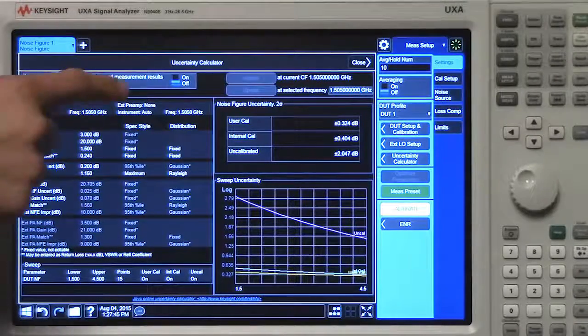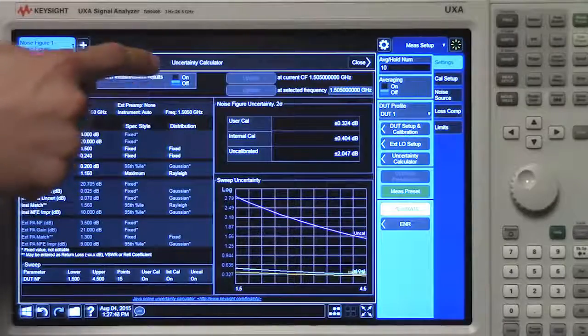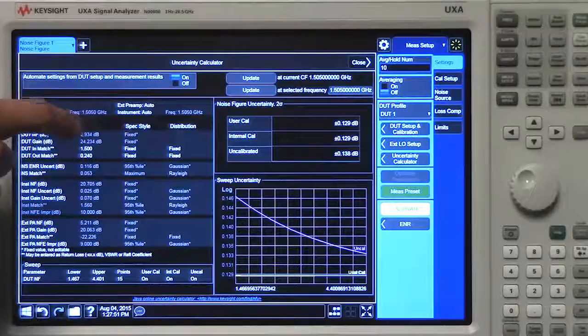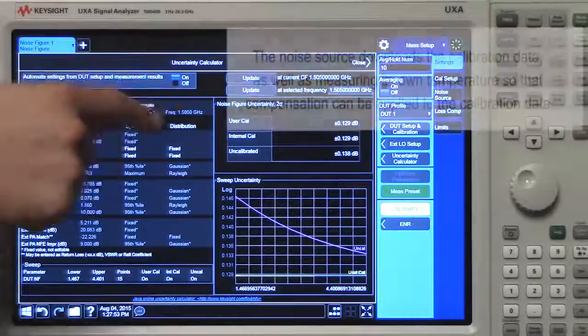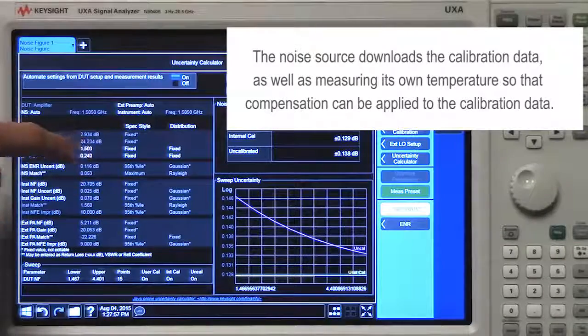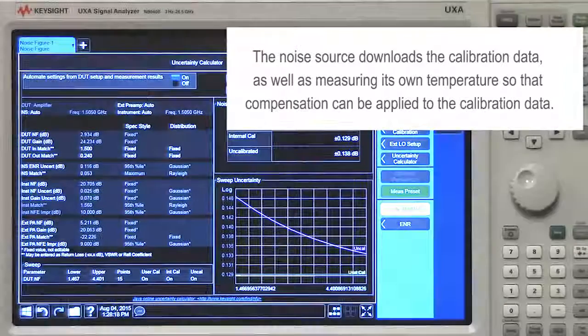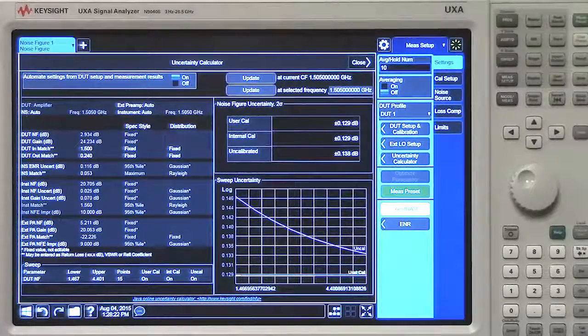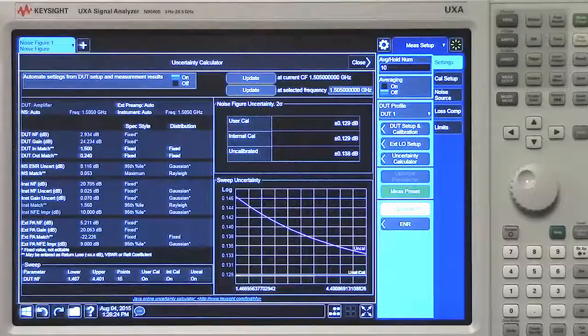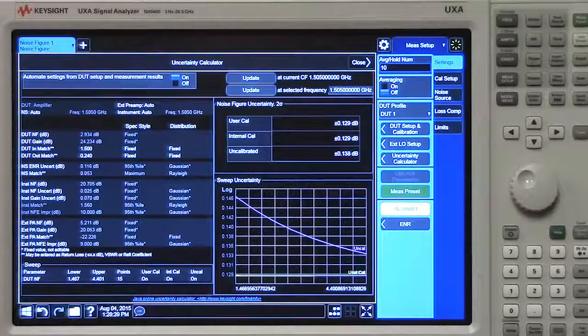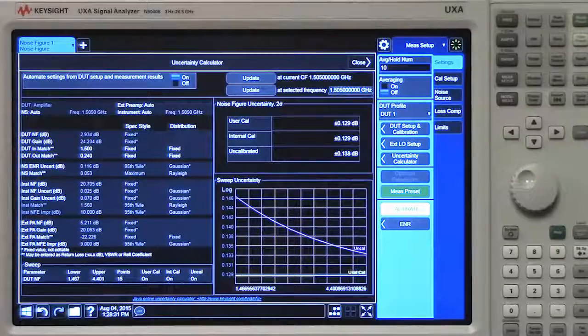At the top, I'm going to toggle the automate settings from DUT setup and measurement results button. As I toggle that, all of these fields that were manual before changed to auto and it loaded the necessary values. Our uncertainty calculator now has enough information to give a reliable total uncertainty. Notice that all we had to do was connect our smart devices and toggle a few buttons.